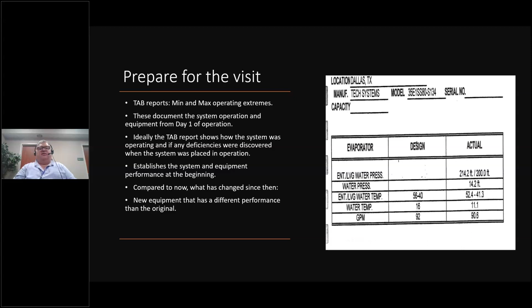You know, they added another chiller because they want colder water. Well, no, that's going to give you more water, but it's not going to make it any colder. Or if they added new equipment that's different from the original, when you do the site walk, you've got this in hand saying, okay, they put this pump in, but now this one's in its place and it's different.